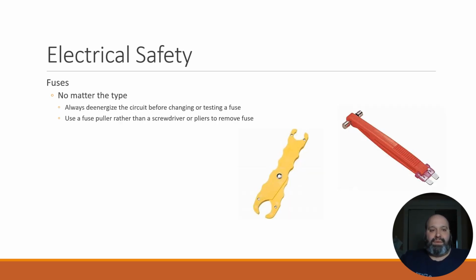So when pulling a fuse, always remember to de-energize the circuit before changing or testing a fuse. Because if you pull the fuse with the system energized, you're going to create an arc flash, which is again more damage. There are several kinds of fuse pullers. It's really ideal to use a fuse puller. Don't use your screwdriver or pliers to pry out a fuse or pull a fuse. That's again more damage. Instead, they actually make these pullers.